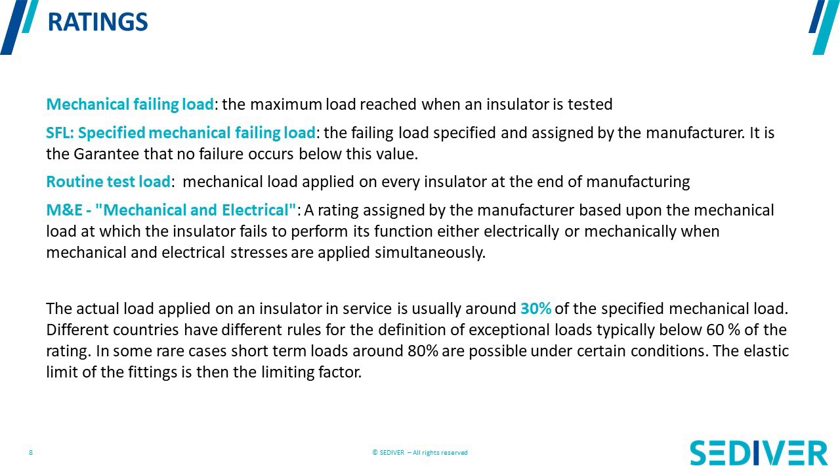so that when you do an M&E test, you do not damage the structure of the material under the specified value. The consequences are not necessarily mechanical, because your insulator might not separate or break in pieces, but you could have a small crack which can be an electrical problem, which is what we call a puncture. We will see that also later on in a few minutes.